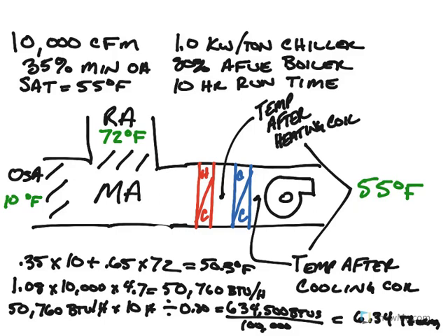So in the first scenario, we didn't have to add any heating or cooling. This one, we're adding some heating, but keep in mind what I saw a lot of you do was they had an answer that had both heating and cooling being added in this scenario. You should never have a heating coil and a cooling coil adding energy to the airstream at the same time. It's one or the other. And if you're ever going out to a building where you see that happening, it's called simultaneous heating and cooling, and it's a problem that needs to get fixed. So if we're adding heat, we're not adding cooling. So if the next question says how much cooling is required, the answer is 0.